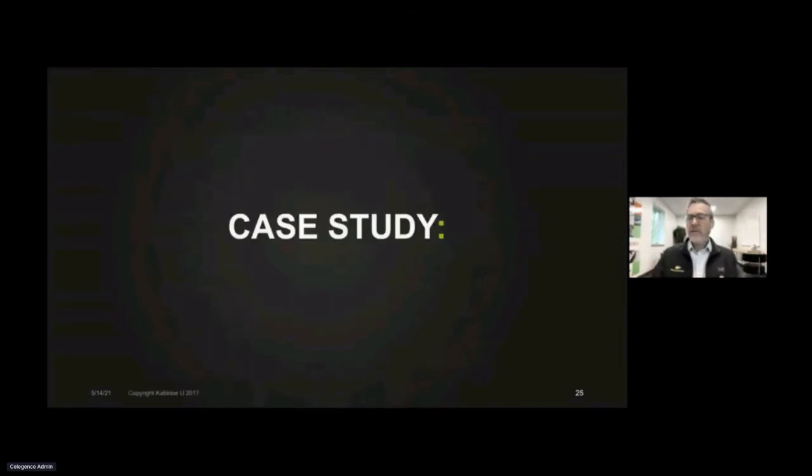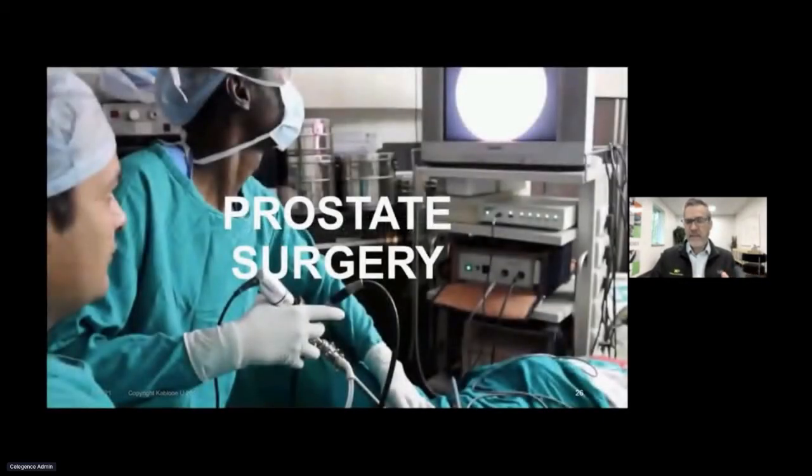And so I want to show a little case study here. In this case study, let's look at a device that was developed for prostate surgery. This is something that we actually did. This is a real case study. So we were taking a look at prostate surgery, and in the beginning of this development process, we're in this early evaluation, in this early research phase. If we think about all of our other design controls, everything that's going on with our quality management system and design controls, we're really in the pre-design control phase right here. We're in phase 0 at this stage of the game.